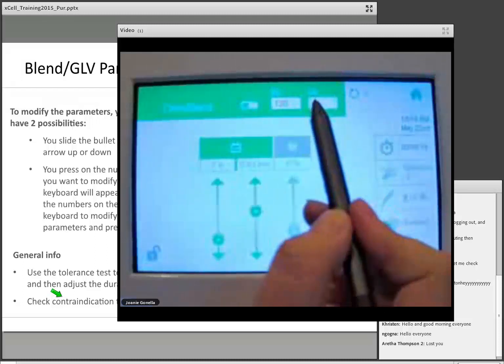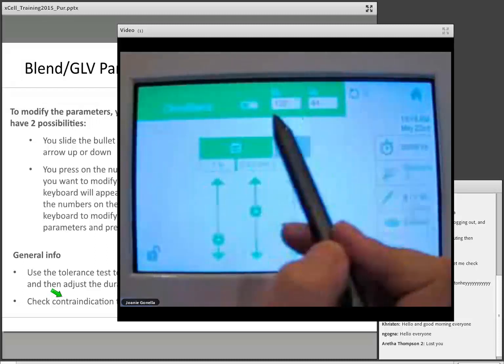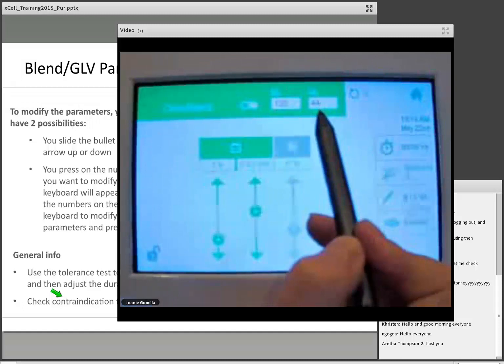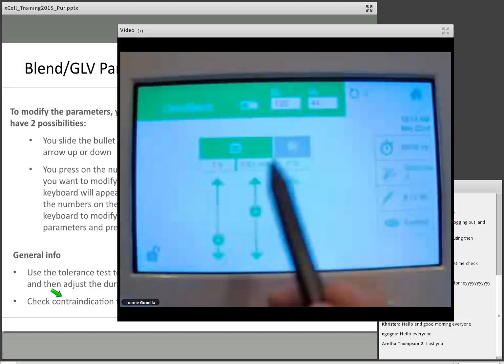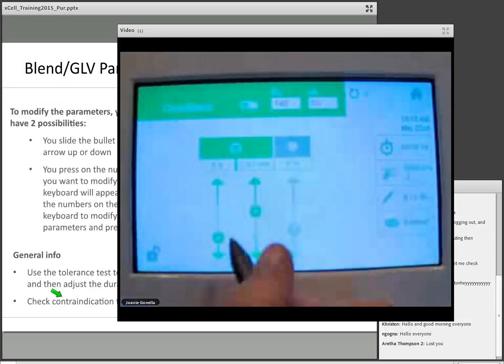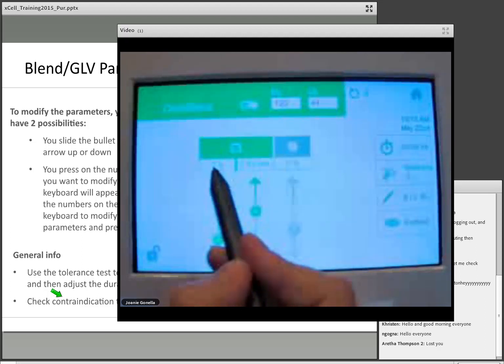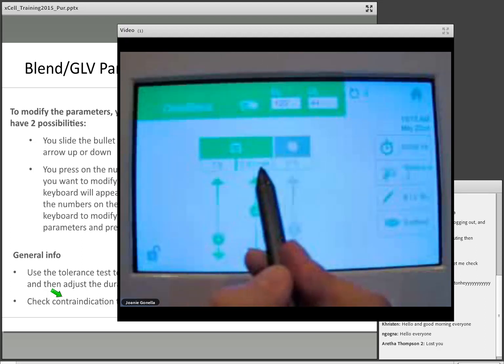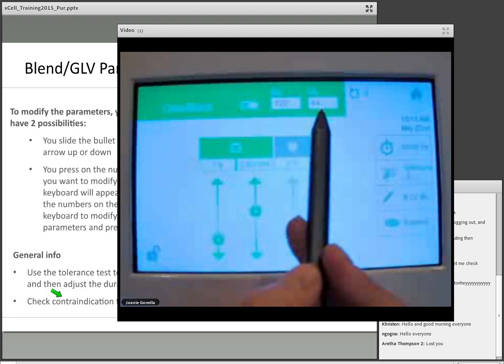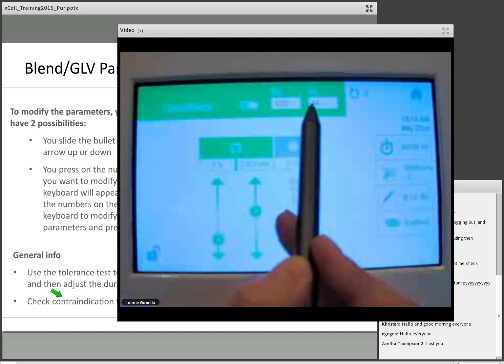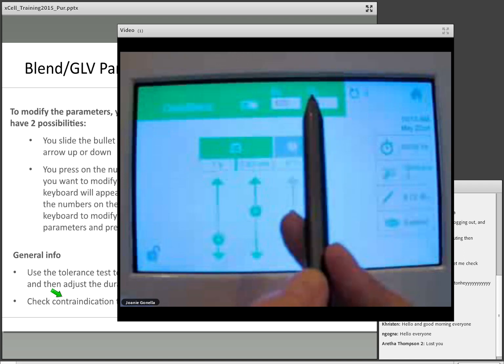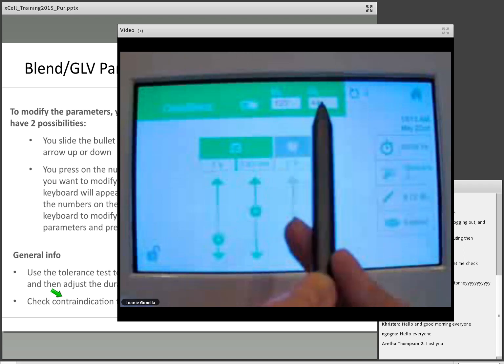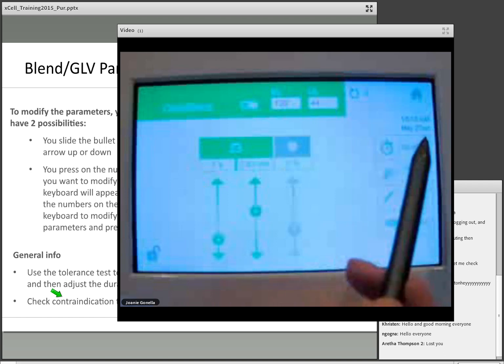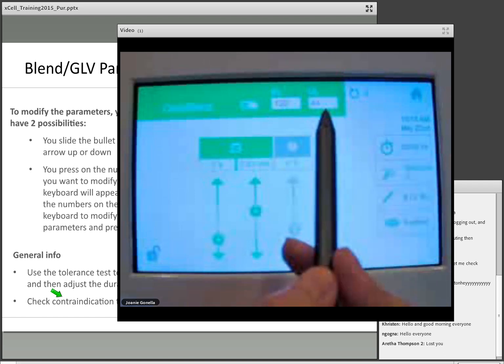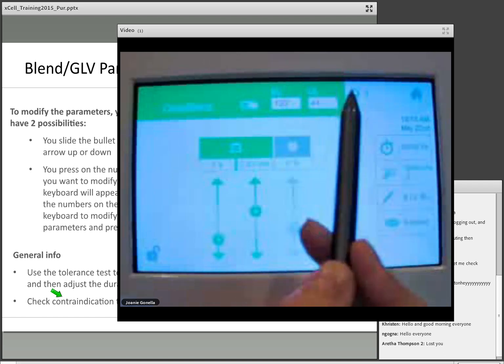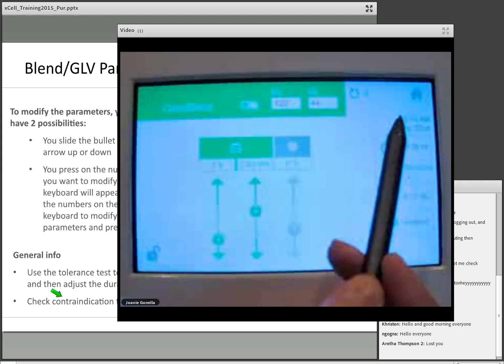But essentially, units of lye, just like calculations of energy level, tells you how much lye you are producing in the follicle using this time and this intensity. So I have 7 seconds. I have 0.63 mA. Therefore, I'm producing 44 units of lye. The units of lye averages are 20, 40, 60, 80. So 20 is for fine hair, 40 is for medium, 60 is for coarse, 80 is for extra coarse.